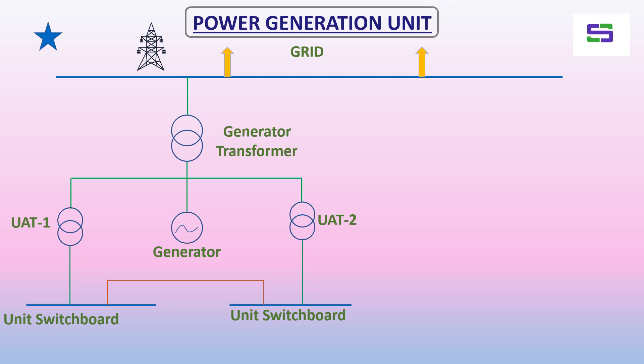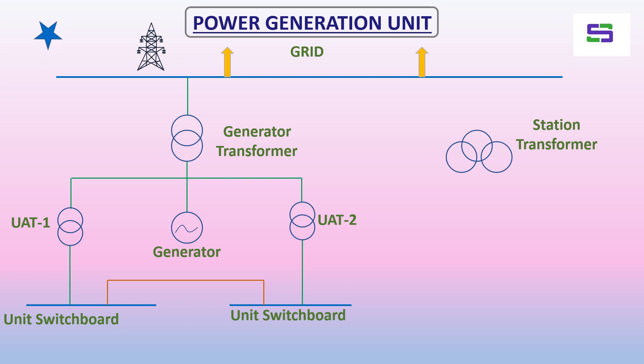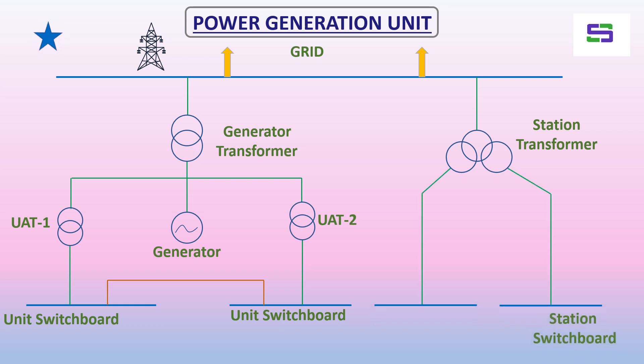To feed the common auxiliary loads or provide startup power for the power plant, we need a station transformer. The station transformer draws power from the grid through the switchyard and caters the power supply to the station switchboards connected with it. It may be a two-winding transformer or a three-winding transformer depending on the requirement.